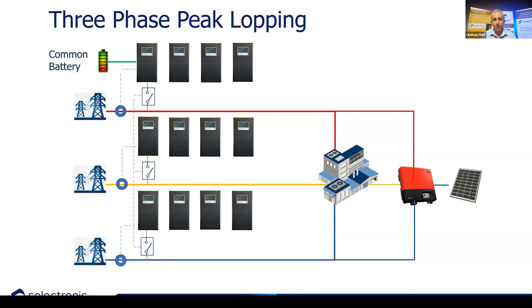Because if it's not delivered, your return on investment is going to take a real dive south, and that's just not acceptable in what we're trying to do here. So up to 240 kilowatts, in that situation, it would be a 120 volt DC system, and we could use the PowerPlus lithium batteries, or we could use the new Selectronic SelectCell lithium batteries to achieve that solution. We don't care how much solar you have in this system. It's totally separate. It's going to be self-consumed as normal and export if required and if allowed.